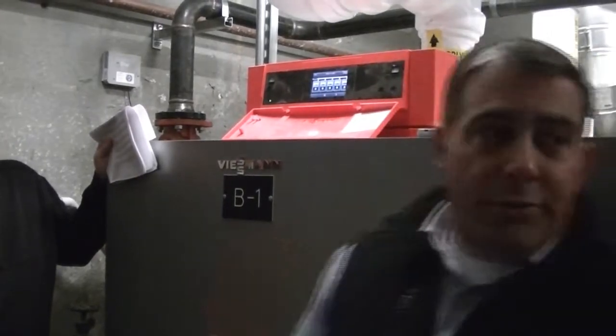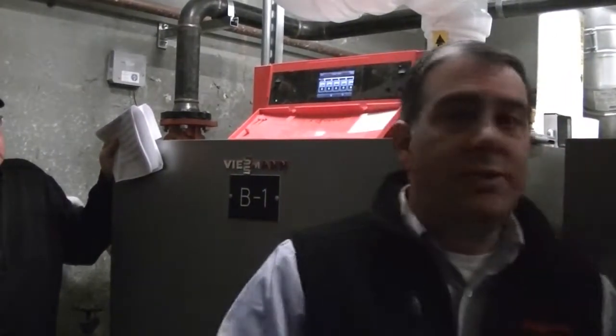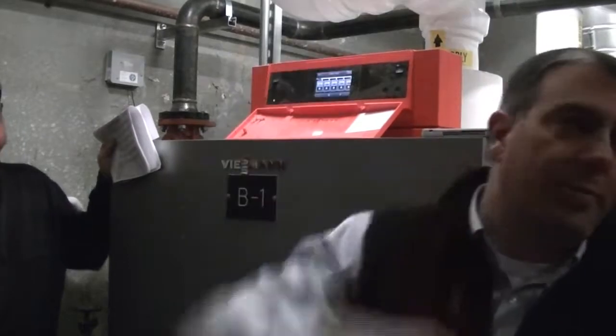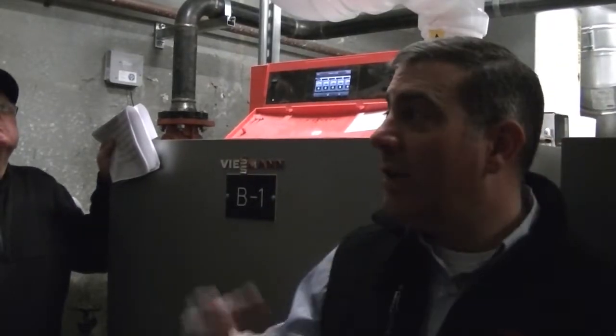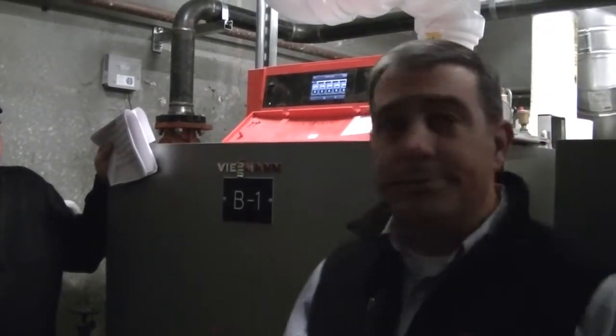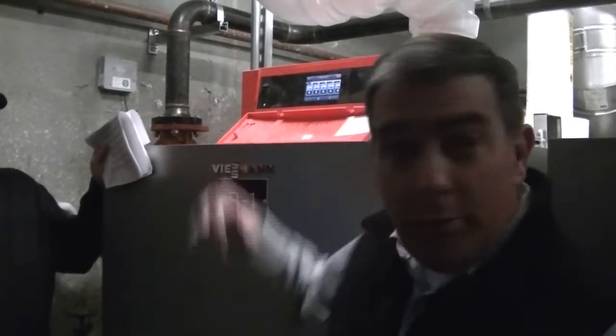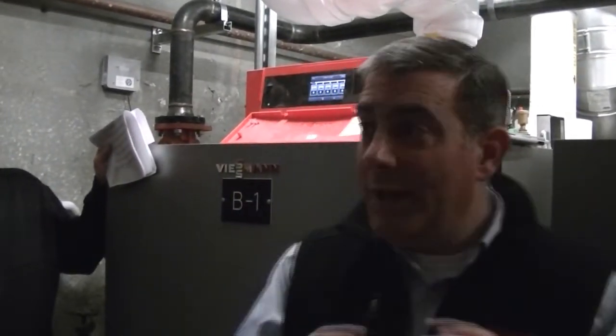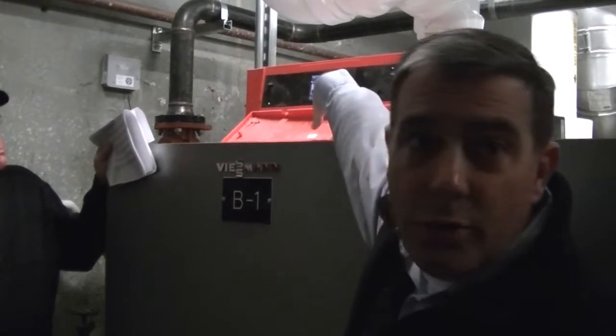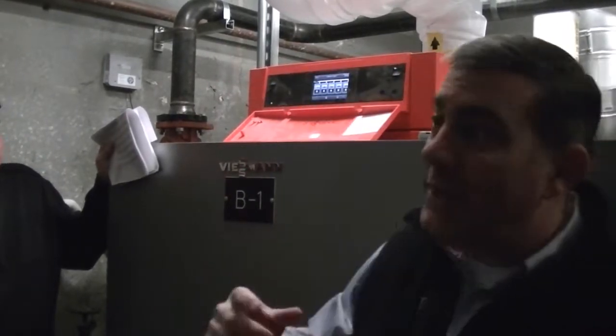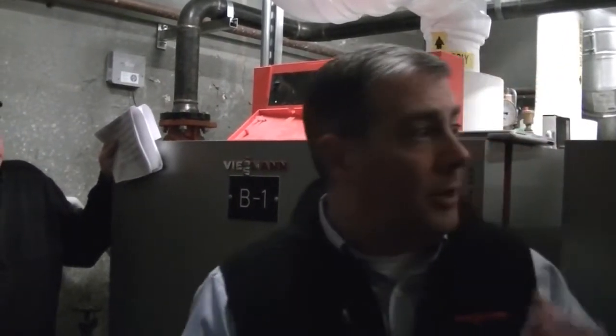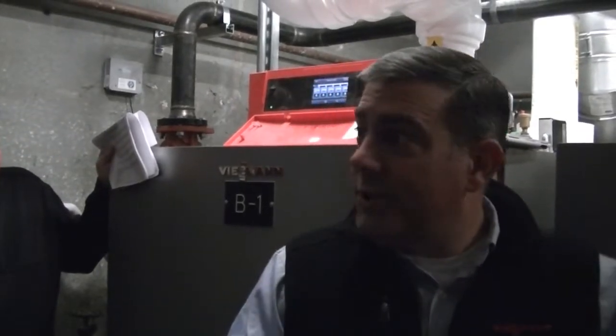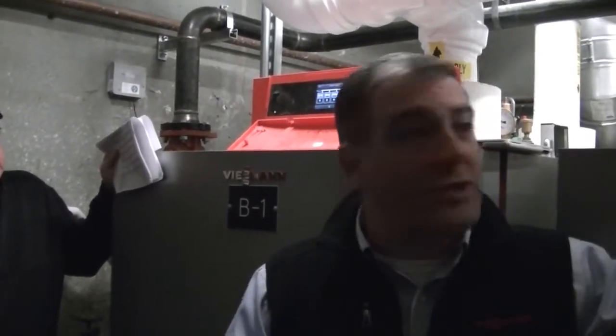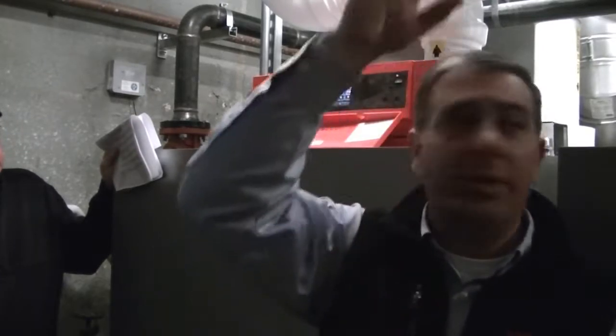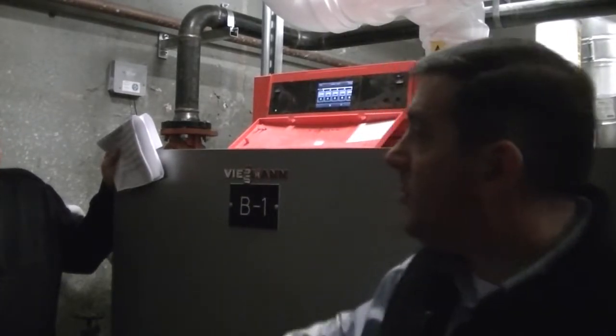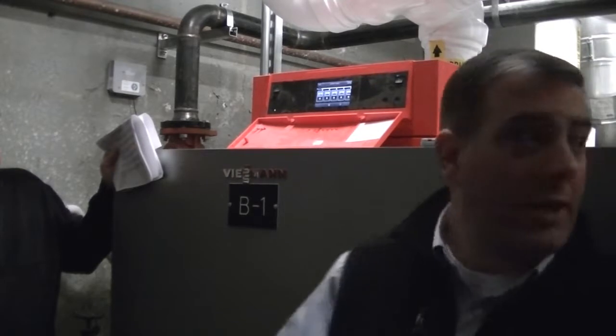If you have a burner failure or a fault, or somebody knocks the outdoor sensor off the side of the building or knocks one of the supply sensors off the pipe, you will get a fault in the system and it will show up everywhere. The first place it shows up is on the boiler itself that has a fault, but that'll also get communicated back to this control here, okay? And it'll be a plain text fault. It'll tell you that the fault is either with participant 2, or participant 3, which in this case is boiler 3. It may tell you that it's simply an outdoor sensor fault. It may tell you that it's a burner lockout fault, and it'll tell you exactly what that burner lockout failure is.